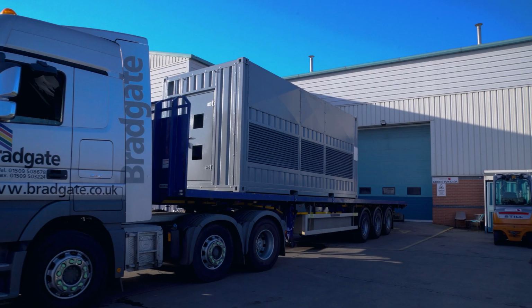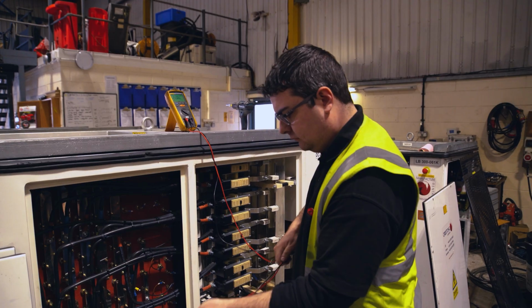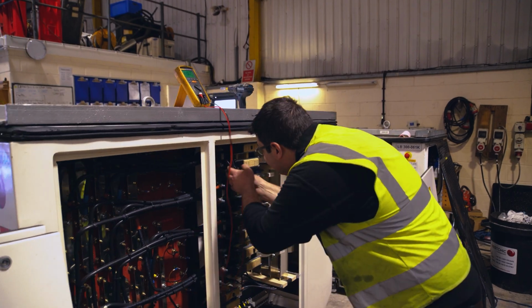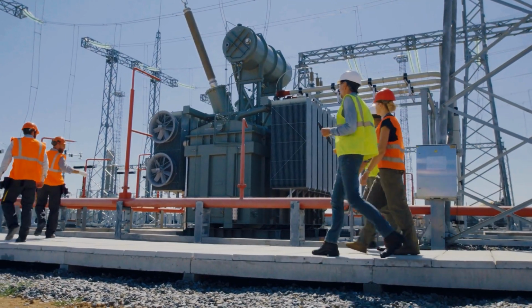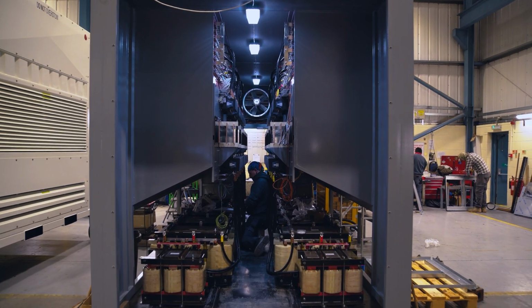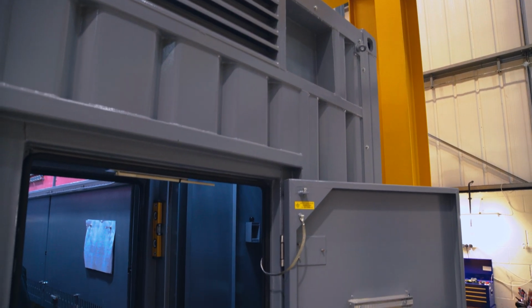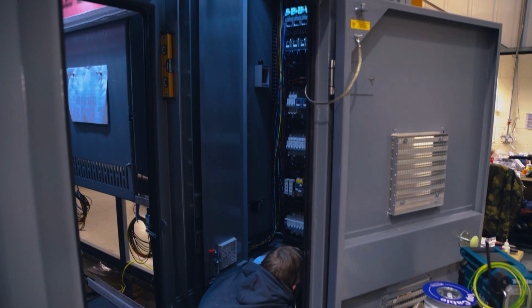Crestchic Loadbanks is a market leader in the design, manufacture and rental of industrial load banks. We've been producing load banks for testing diesel and gas power generators for more than 35 years. Our load banks test standby generators all around the world to ensure that when called upon, they can operate effectively and safely at the correct voltage, capacity and frequency.